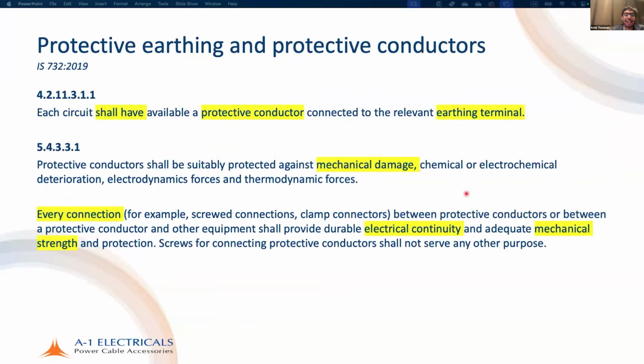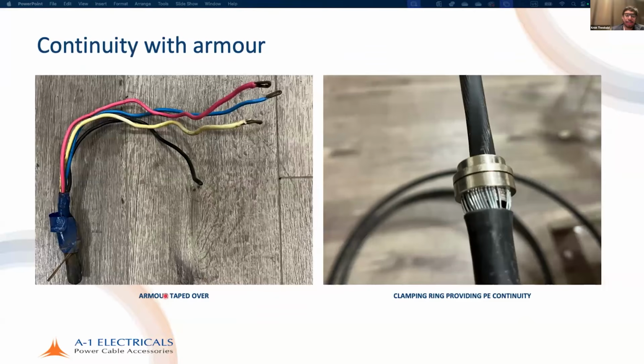None of these requirements are being met. There's no protection against mechanical damage, no electrical continuity, no mechanical strength, and of course, all the requirements for ingress protection are just outside the window. Also, it is extremely unsafe because people can touch it, it can come loose, it's very dangerous.